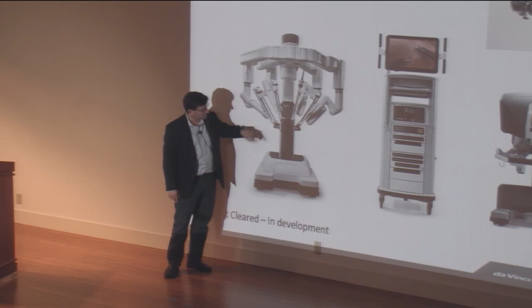These instruments themselves are actually steam sterilized. They go through a fancy washing machine called a washer disinfector that cleans them, and then they go into a sterilization device. You can also clean these manually with scrub brushes and syringes full of water. And then there are some things that are single use, used once and disposed of. There are the seals that contain the gas for the body and so on.